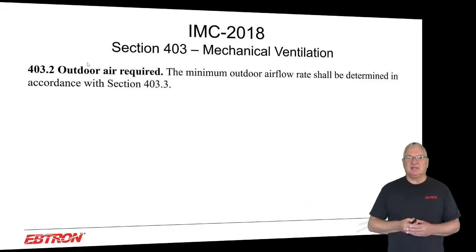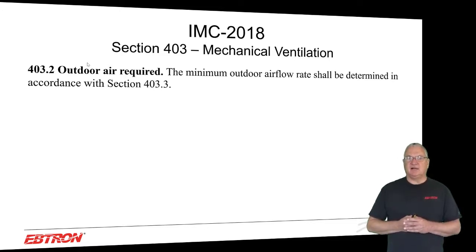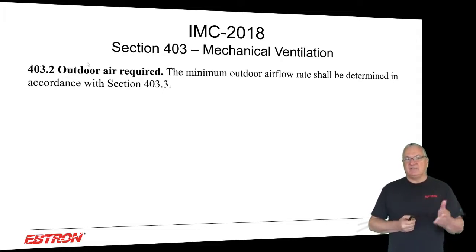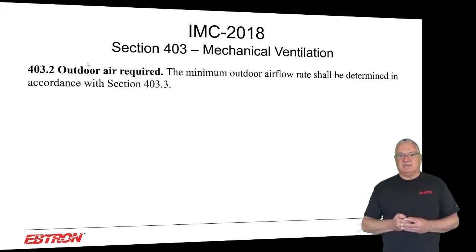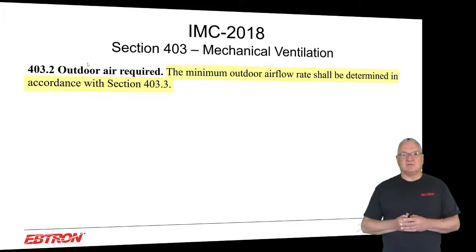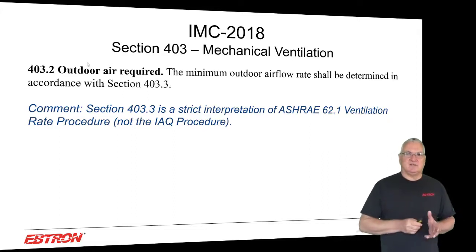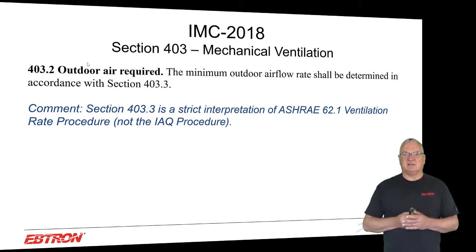When you look at the IMC 2018 — regardless of what version your state has adopted — pretty much all versions still reference the same ventilation requirements of Standard 62, because those ventilation requirements changed in 2004 and really haven't changed since. The minimum outdoor airflow rate shall be determined in accordance with section 403.3. If you sit the IMC ventilation requirements next to the ventilation rate procedure, you'll quickly realize they're the same thing.